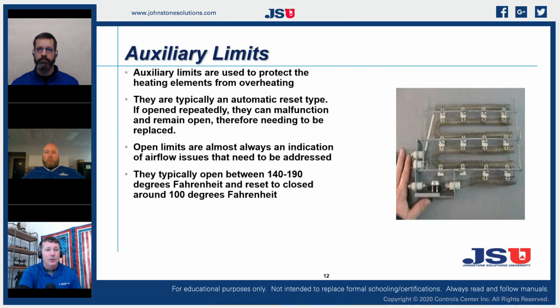Auxiliary limits, we're going to have two different styles of limits on an electric furnace. We're going to have an automatic reset, and then we're going to have a manual blow. That manual blow is just like a fuse. When it pops, it's a one-time blow because it got really hot. Our auxiliaries are typically around 150 degrees for most of our brands. It can go up to around 190 for these automatic ones, but most of the time they're going to be around 150, and then they're going to reset back around 100 degrees. But the same thing with those.